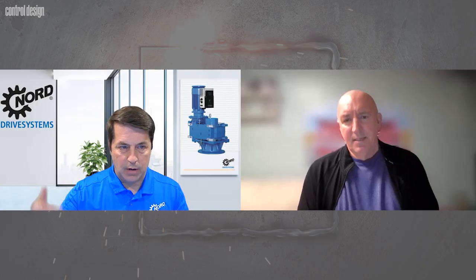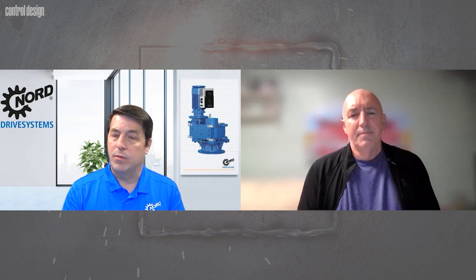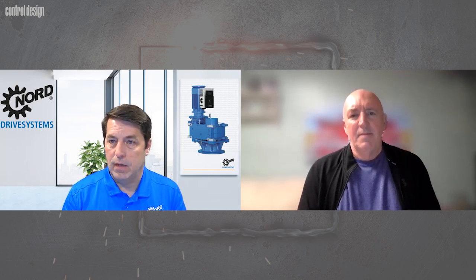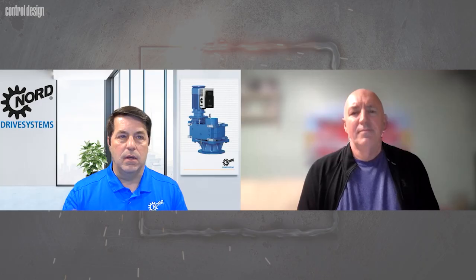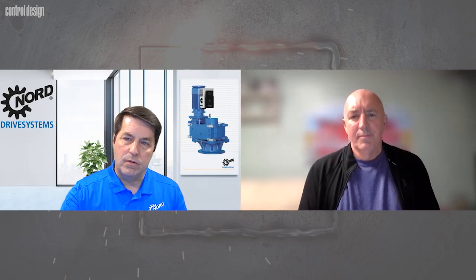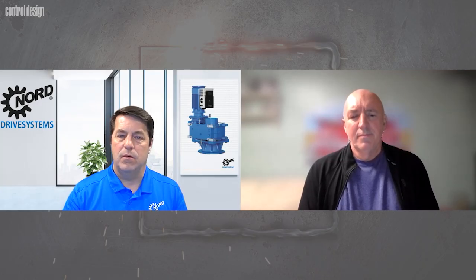And we're asked, as experts in our drive systems, what do I need to be looking at? So if you include our VFDs on there, you immediately pick up a ton of data. Power usage, output current, field current, your torque current, temperature data from the motor, ambient temperature data, particularly if you have a temperature sensor that's wired in externally, temperature of the VFD. Is it overheating? You get error codes back from the VFD for its operation, the operation of the drive system.